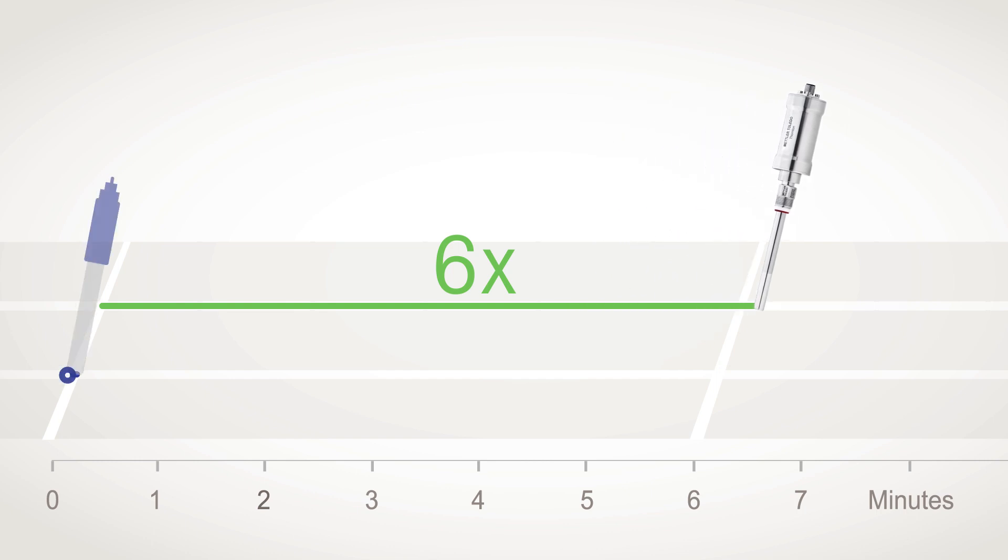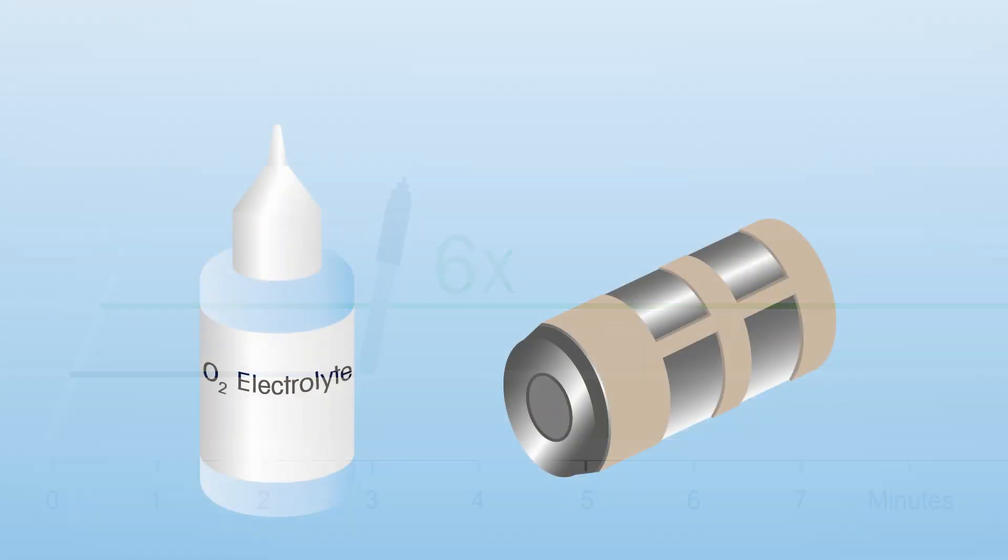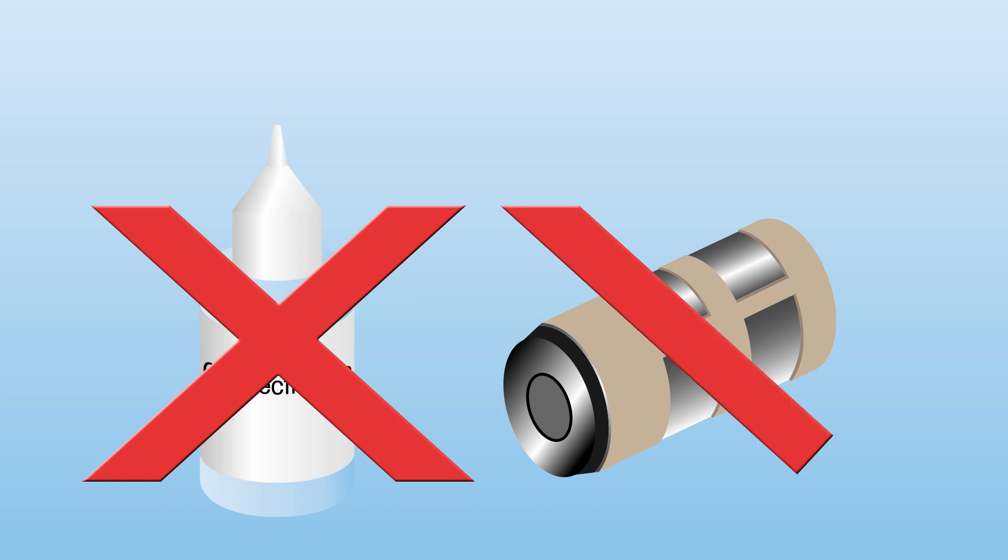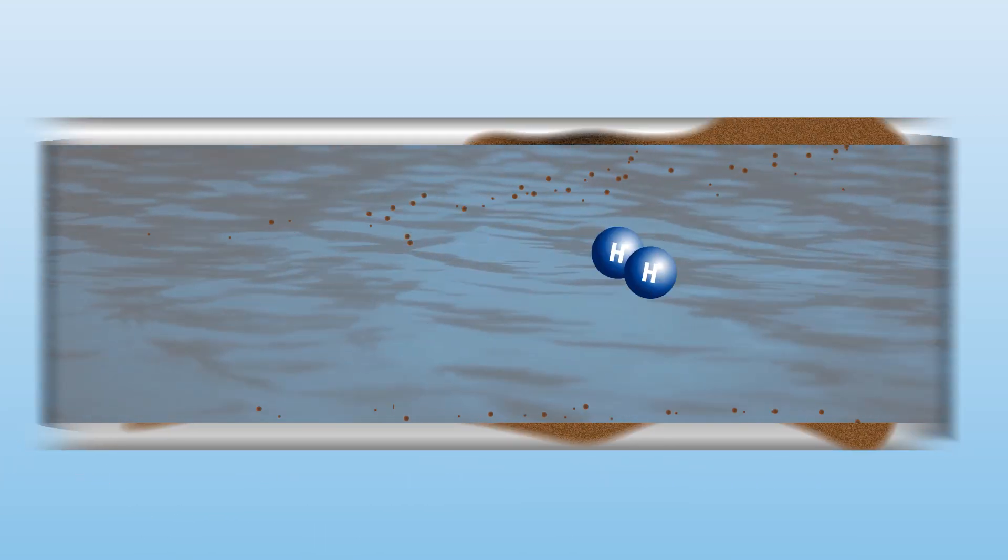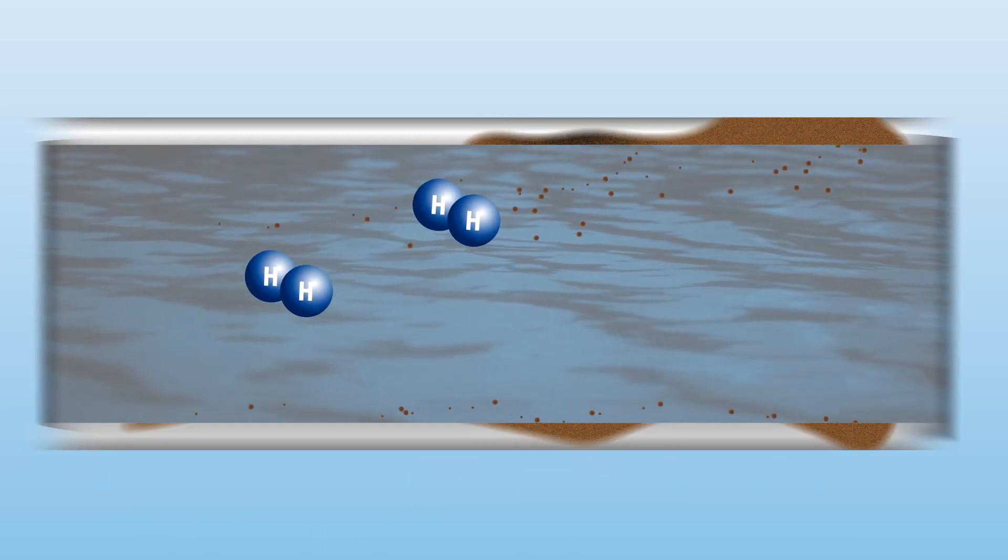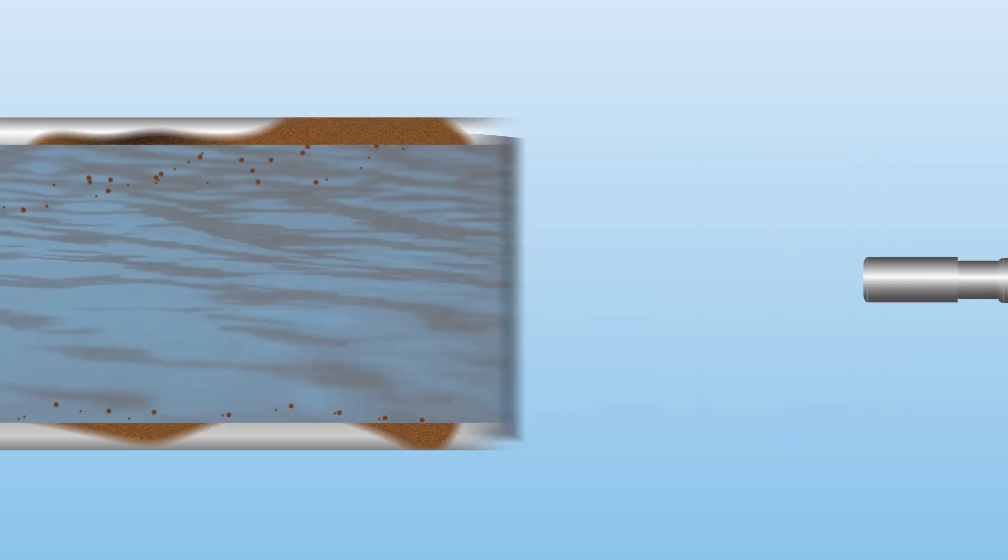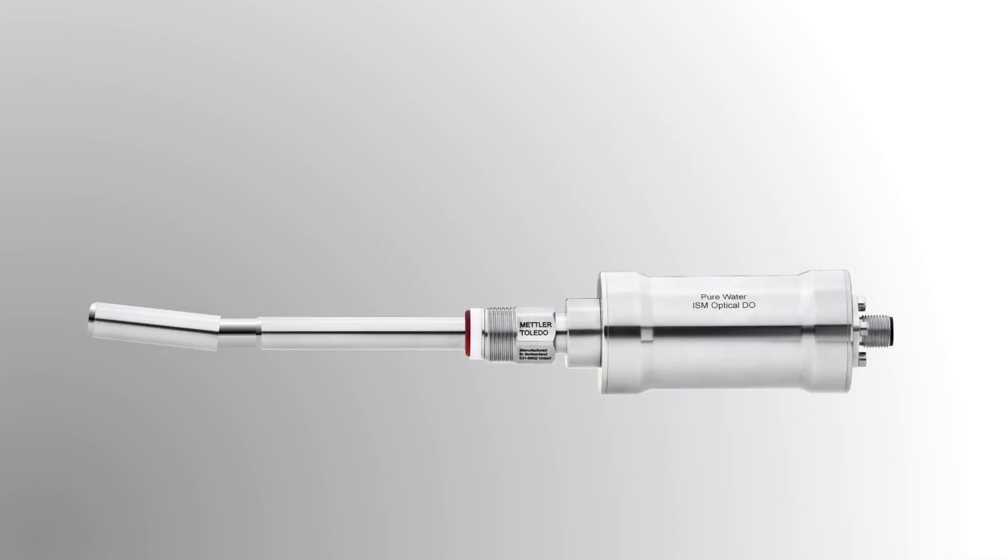The optical DO sensor also does not use electrolyte or a membrane, so it's not sensitive to flow or susceptible to damage from particles and dissolved hydrogen interference. There is no interior body to replace, and service is required only once a year to quickly and easily replace the one-piece opto-cap sensing element.